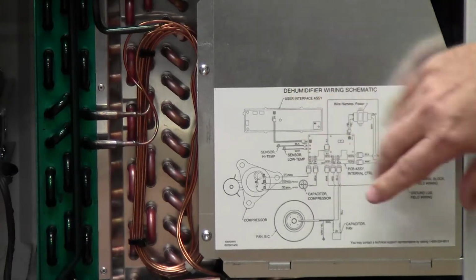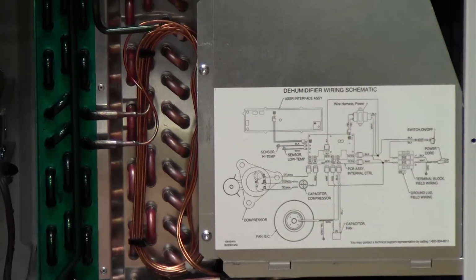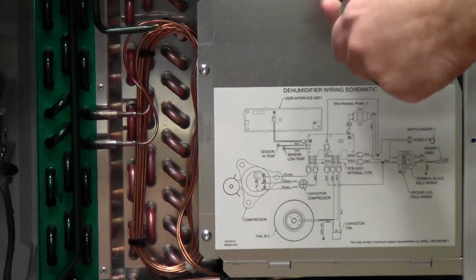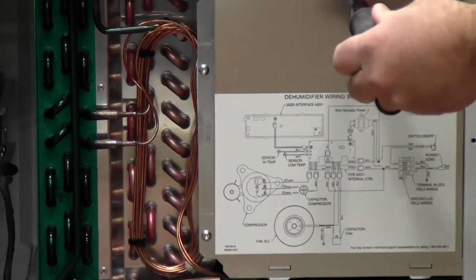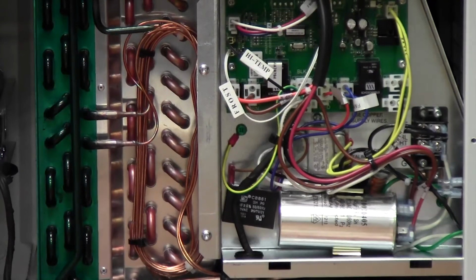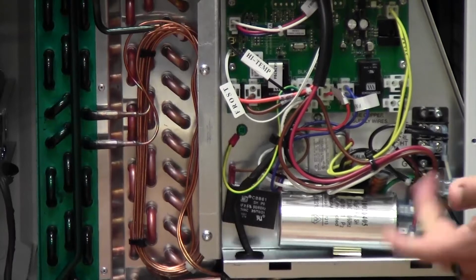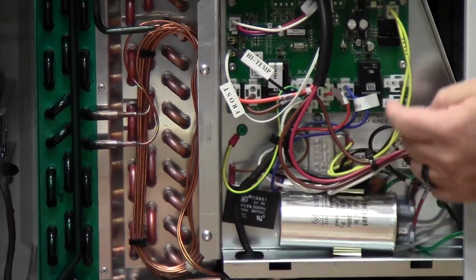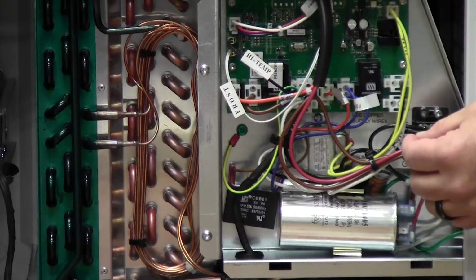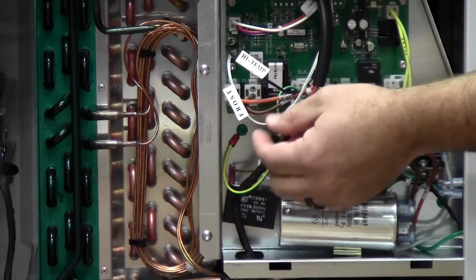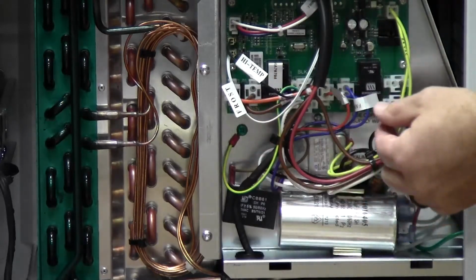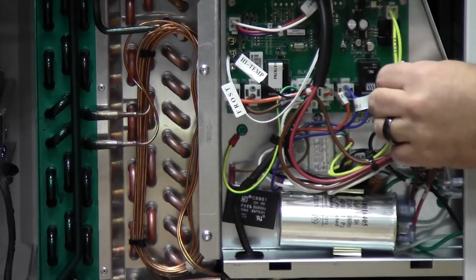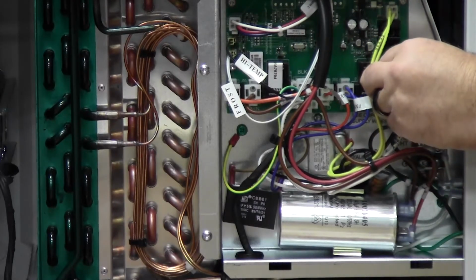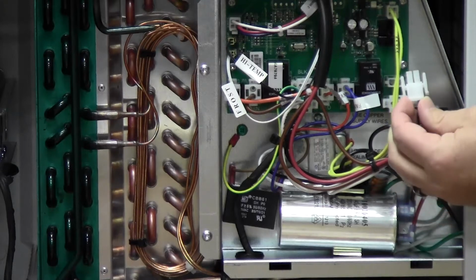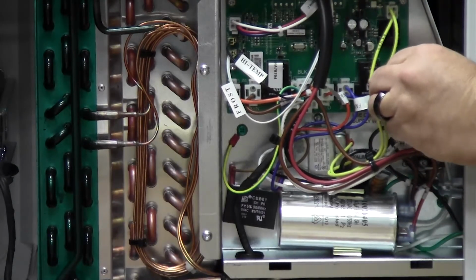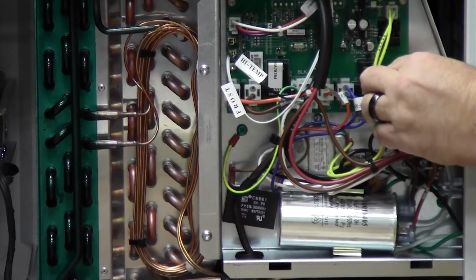Now on this side here we have the electrical panel, and you can see we have a nice diagram that shows you the electrical schematic, and I'll take the one screw off here. And you can see all the components are readily accessible. The run capacitor for the compressor, the transformer and circuit board are all in here, readily accessible for you to service. Everything is labeled real nicely so you know which wires go into frost sensor, high temperature cutout, fan, compressor, all those are nicely labeled. All the terminals that we use now, all the connections are a Molex type connection that have a positive engagement, so they click into place, so they can't rattle free in shipping or anything else. They'll hold nice and tight.